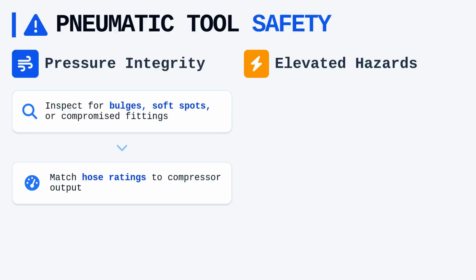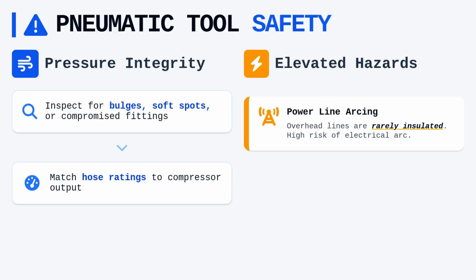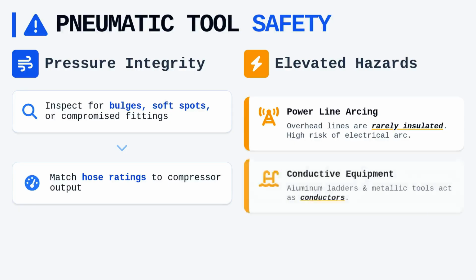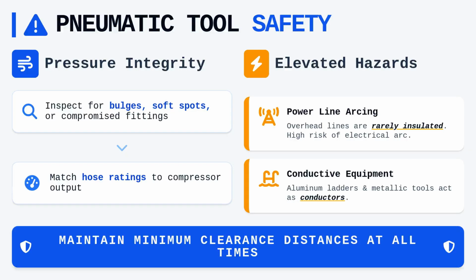When moving outside to rooftops or elevated positions, the danger is amplified by the presence of overhead power lines. These lines are rarely insulated in the way household wiring is, and coming into proximity with them while holding metallic extension tools or aluminum ladders creates a massive risk for arcing. Always perform a situational assessment before raising any equipment, maintaining the required minimum clearance distances to keep yourself and your crew safe.